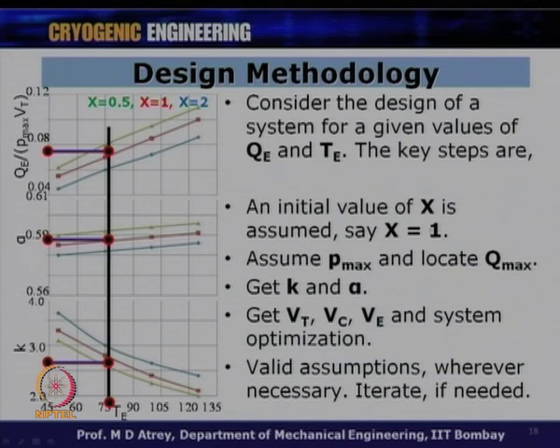This design procedure is illustrated with a tutorial: designing an alpha-type Stirling nitrogen liquefier using Schmidt analysis and Walker's chart. The working gas is helium, the capacity is 10 liters per hour of liquid nitrogen, maximum allowable pressure P_max is 40 bar, and the prime mover speed is 1440 rpm. The first step is to calculate the required cooling effect QE.